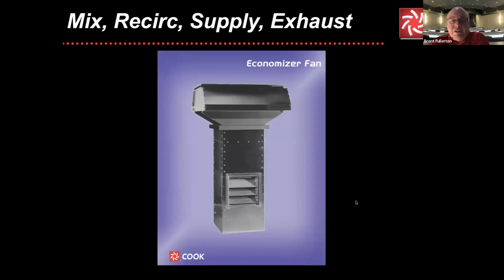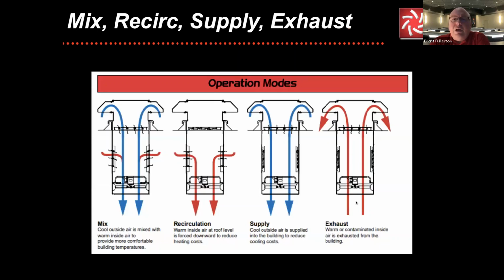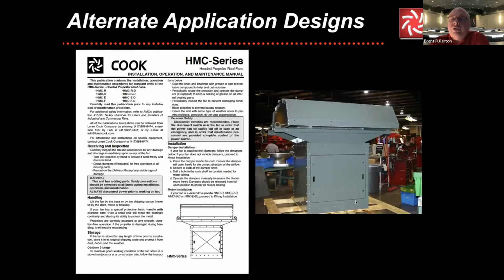Now let's look at some specialty designs and where these really come into play. Airflow has utilized this product through the years. We saw a lot of these for some specific applications. It was nicknamed an economizer fan years ago, but it allows four modes of operation. It can mix the outside air with the inside air. It can strictly recirculate, or it can supply outside air, or it can exhaust inside air. So this one product can do these different operation modes, so it has a very wide range of opportunities. Then also the hooded series that you saw earlier for serviceability can be mounted on what is known as basically a tall curb with an access point, and you can get in and service everything from the roof area, which works wonderfully if you have a flat roof.